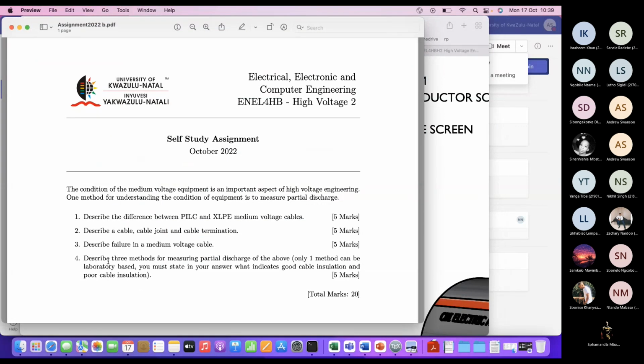Describe a cable joint and cable termination. I think most people were okay with this. A medium voltage cable has to have a conductive component. It has to be rated to the correct current. It also has to have an insulation of a certain rating, as well as needs to be protected from the environment. So I was hoping for a bit more of those elements, didn't get as much as I hoped for.